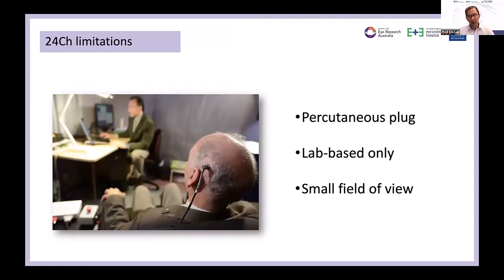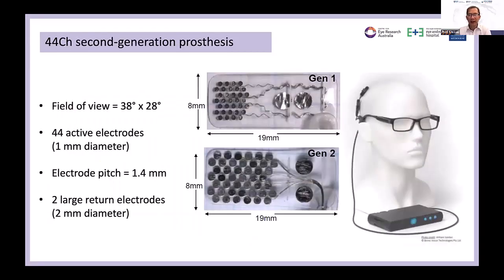Now, of course, this 24-channel device has a number of limitations, but the main limitation is that because it has a percutaneous plug, we can only test it in a lab environment. Patients cannot use it outside or at home, and also it has a limited field of view. And so to improve that, we have developed a second generation device which has the exact blueprint of the first generation, but contains more electrodes, which in turn increases the field of view and also allows better stimulation.